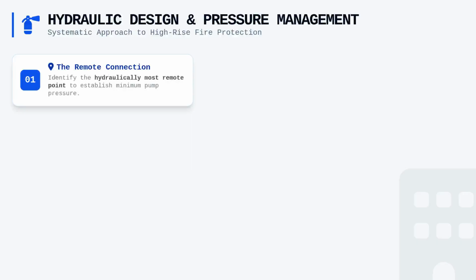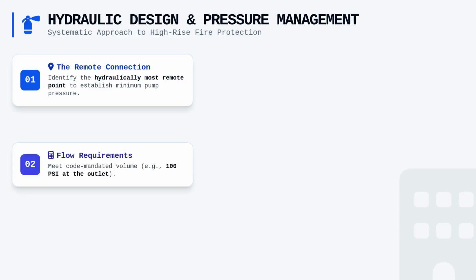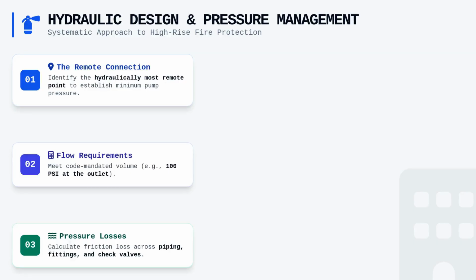The most critical aspect of your design process involves identifying the hydraulically most remote hose connection, which determines the minimum pump pressure required for the entire network. You must calculate the flow requirements at this point, typically dictated by code, to ensure a specific volume at a predetermined pressure, such as 100 pounds per square inch at the outlet.